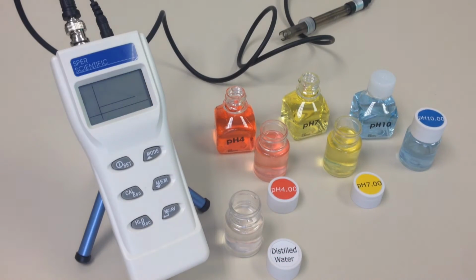All right, today we are going to show you how to calibrate the Sper Scientific pH meter 850055 and 850056 and how to handle the error 13 message. Now, if you do see the error 13 message, that's because something happened during the calibration process and you're going to have to reset the meter back to factory settings.